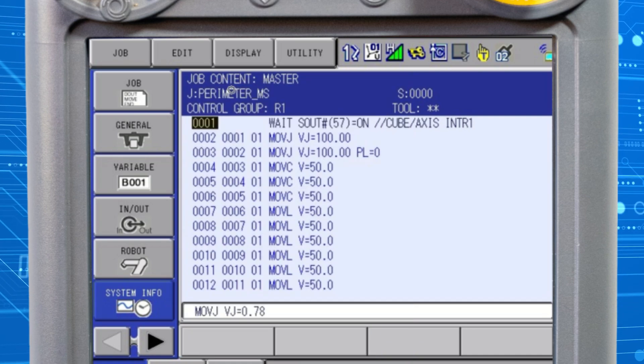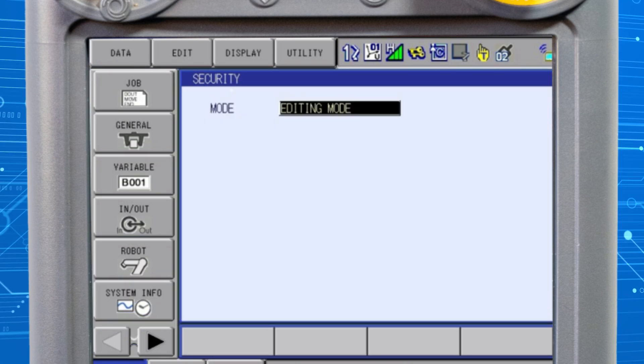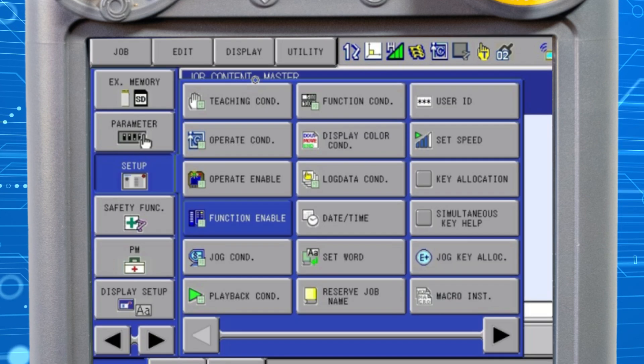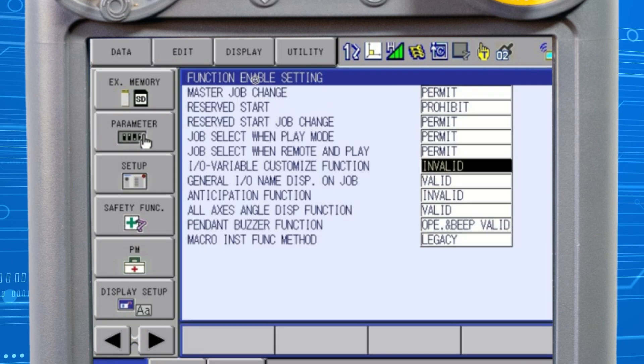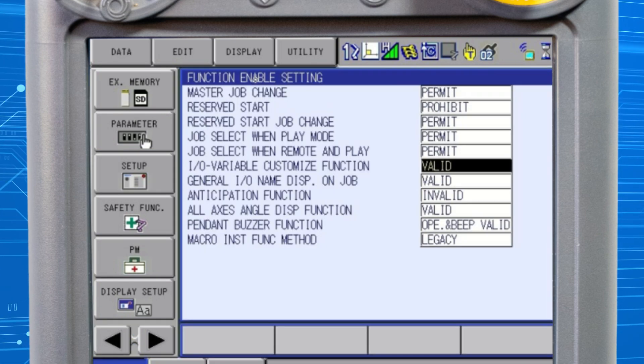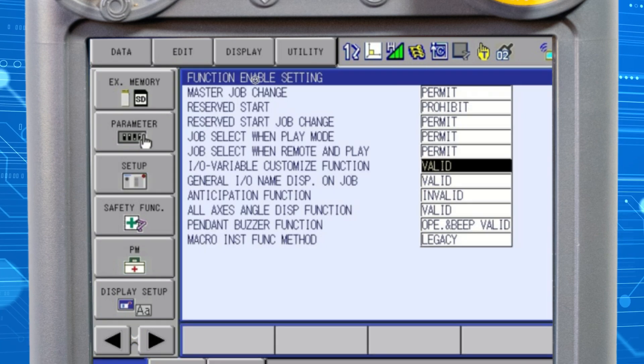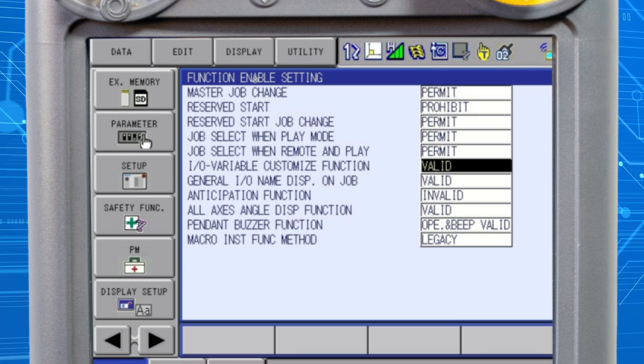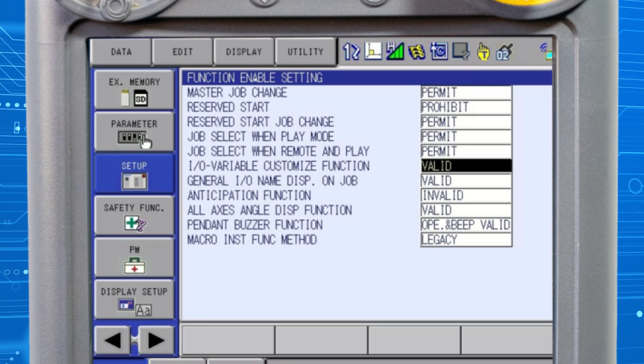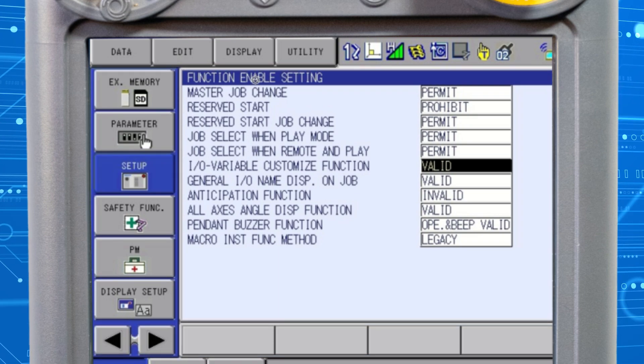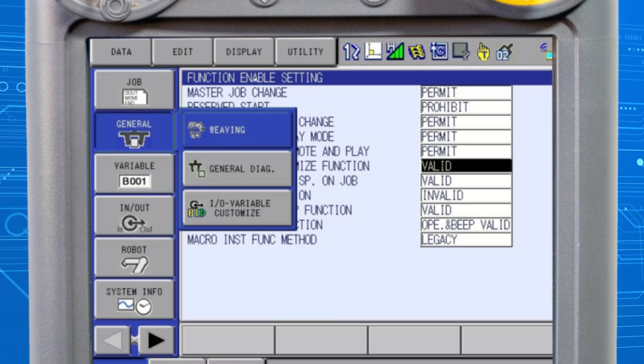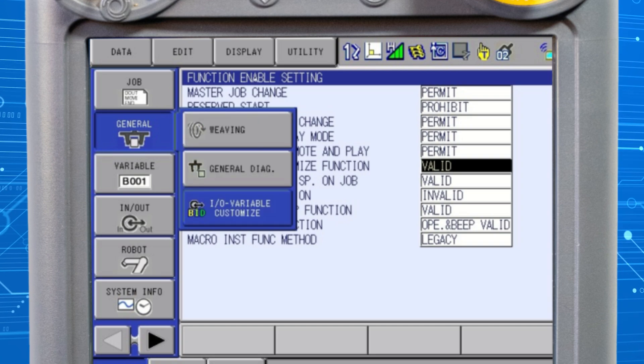To enable, firstly you must have your security settings set to management mode. From here, open the function enable menu. Place the cursor on IO variable customize function and change the field to valid by pressing select. The IO variable customize button will now be displayed and available.